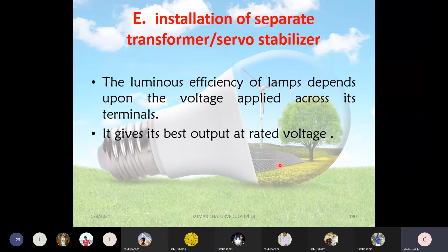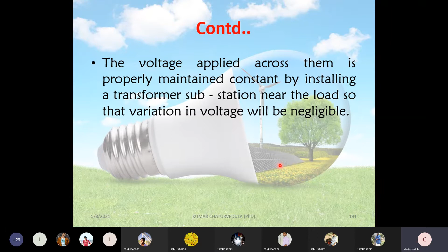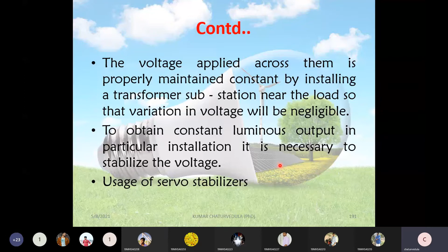So if required, you can install a transformer near the load so that there will be no voltage fluctuations or variations. Sometimes there may be a necessity to install a stabilizer also to reduce the voltage fluctuations. The stabilizer is usually a servo stabilizer. A servo stabilizer is nothing but a servo motor control stabilizer which regulates the fluctuations in the input and gives the proper rated output. So that is done by our servo stabilizer.